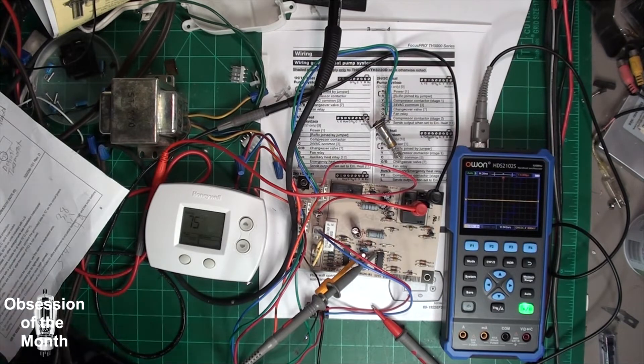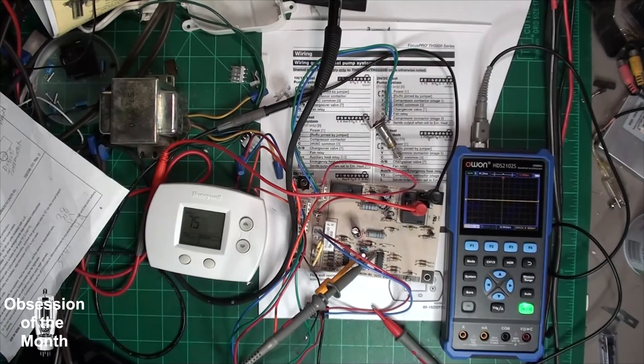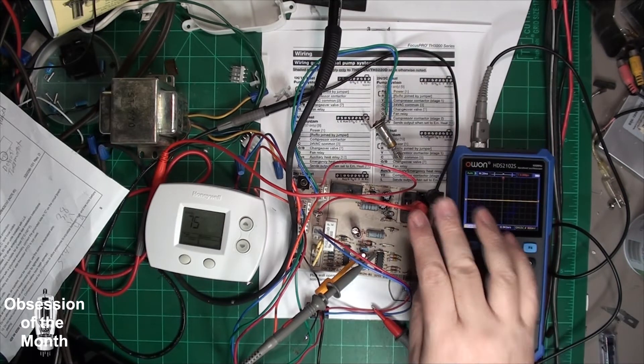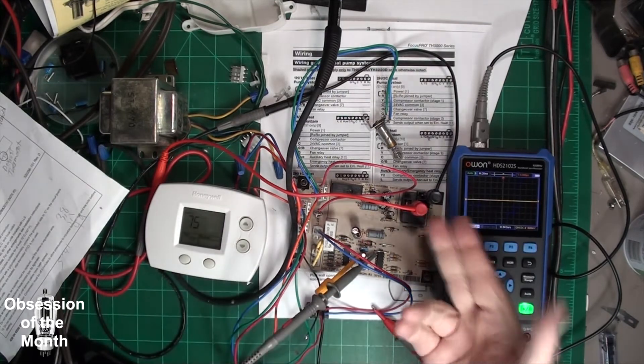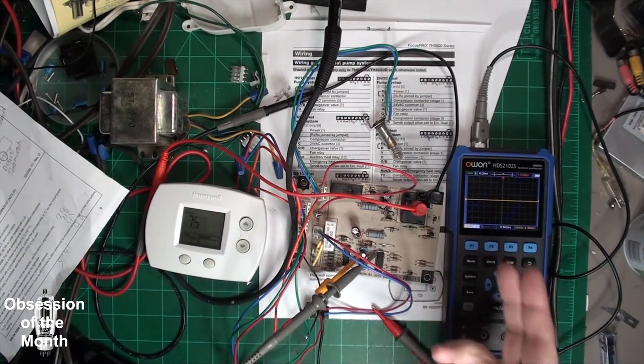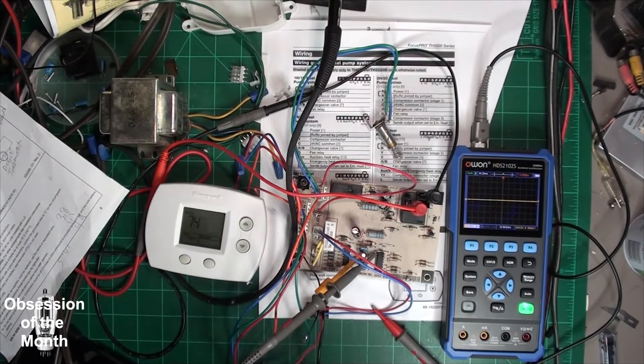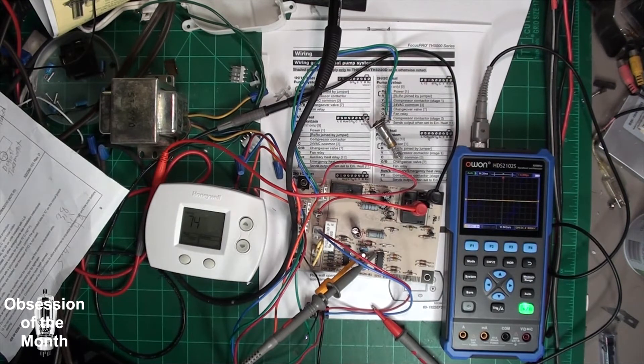The light here is your reversing solenoid and this is hooked up to a continuity tester, so when I turn on continuity you're going to hear a beep and I'm going to show you basically how this thing should work.